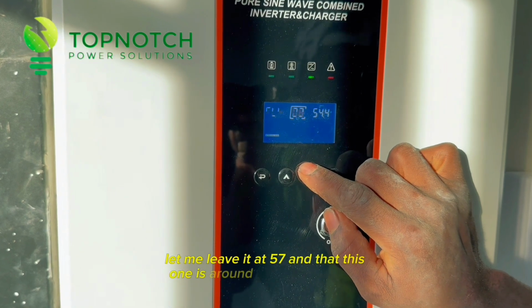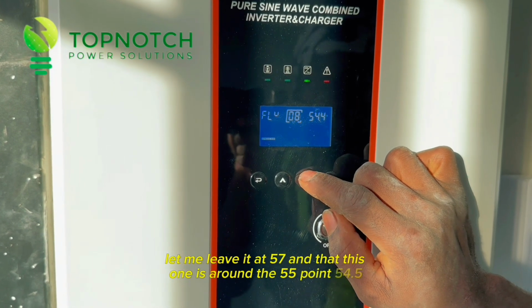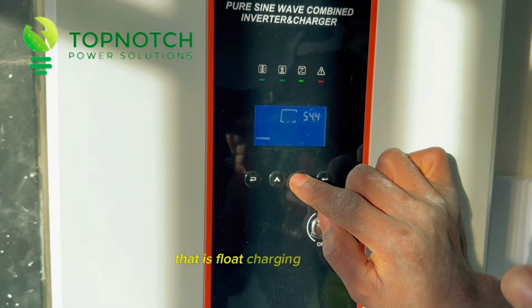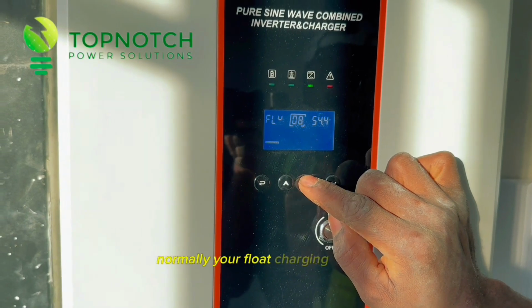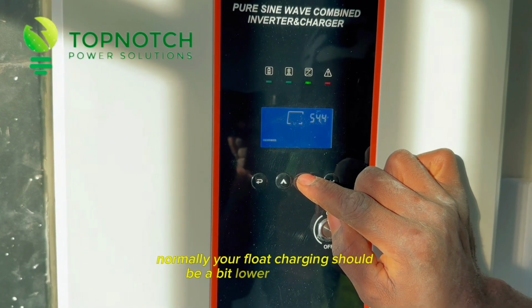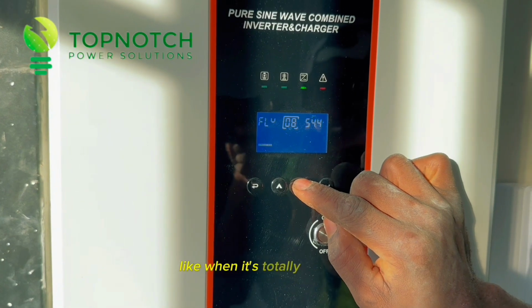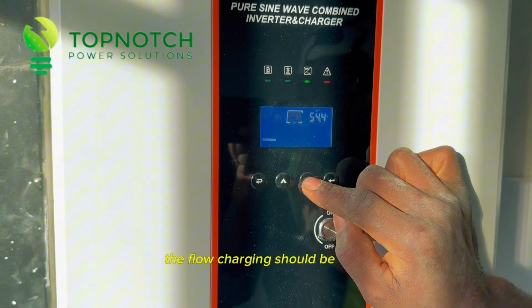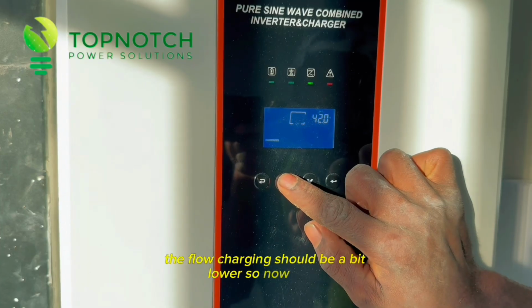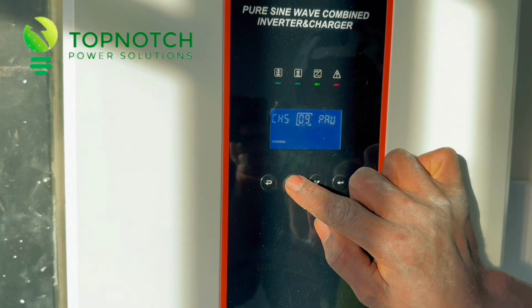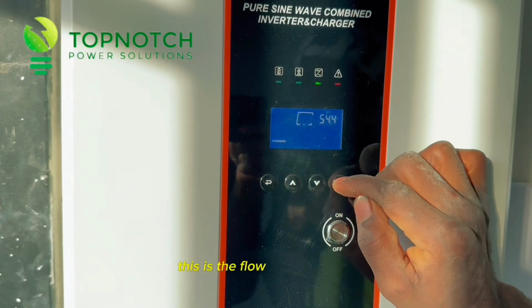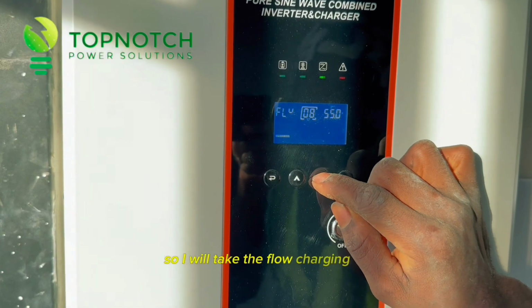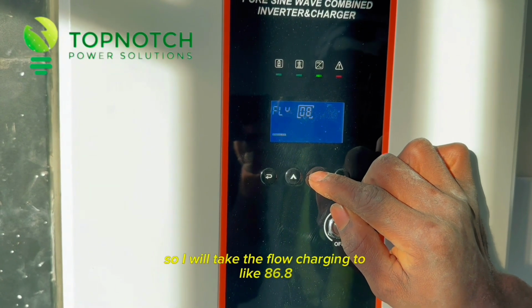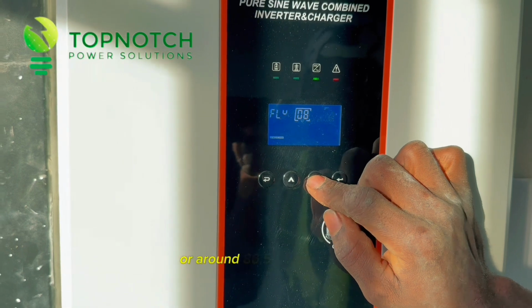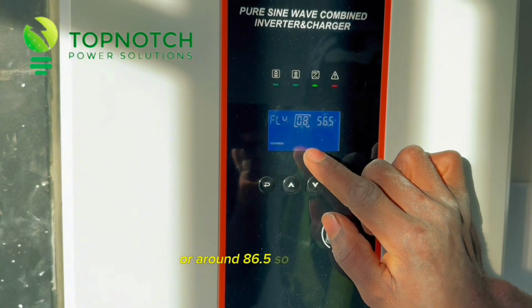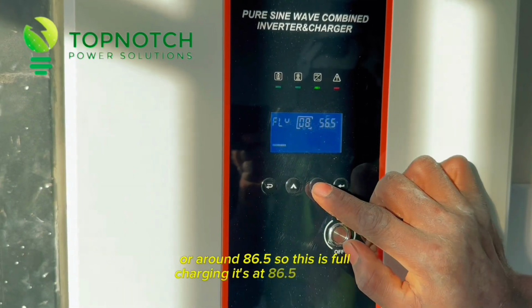And this one is around 54.5. That is the float charging. Normally your float charging should be a bit lower than the full charge, when the battery is totally filled up. The float charging should be a bit lower. So this is the float charging here. I will take the float charging to around 56.5. So the float charging is at 56.5 right now.